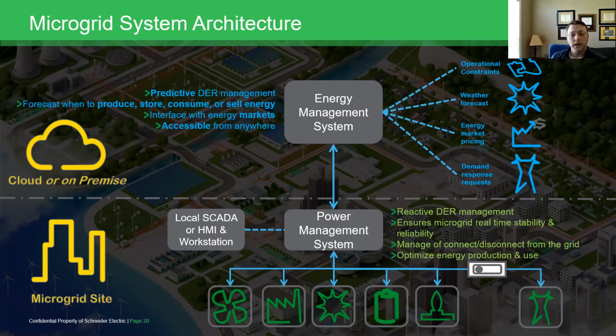First, it looks to see if the utility grid is present or not. If the utility grid disappears, it steps into action and physically isolates the site from the utility grid. Once isolation has occurred, it brings up on-site generation assets and matches load and generation together. Finally, when it sees the utility signal return, it reconnects the microgrid once it has synchronized it to the utility grid—doing all of this in a very safe manner.